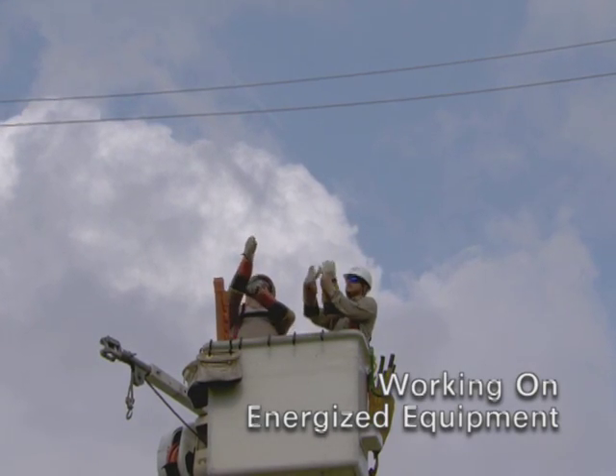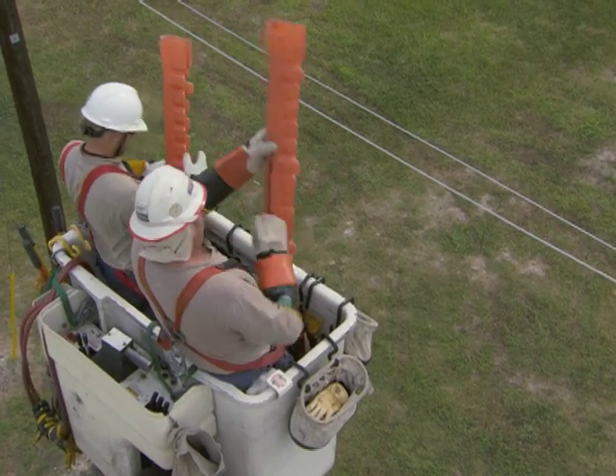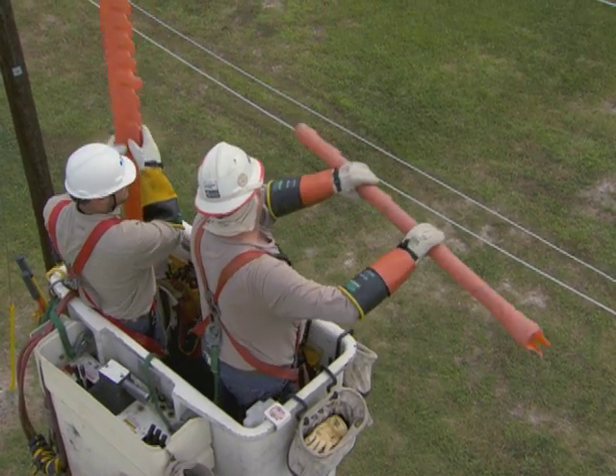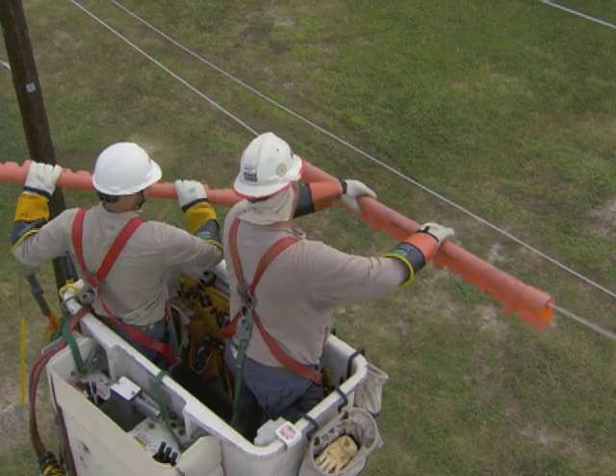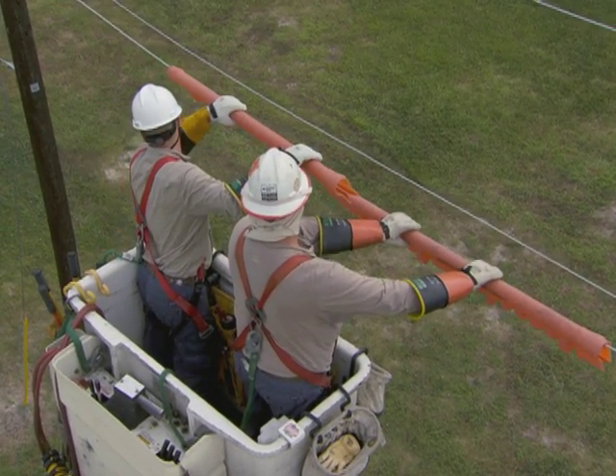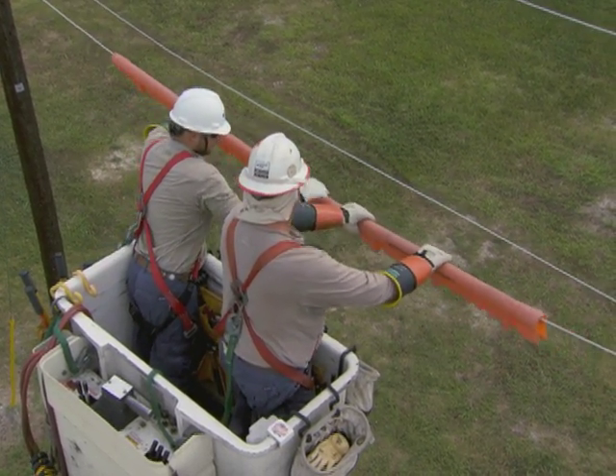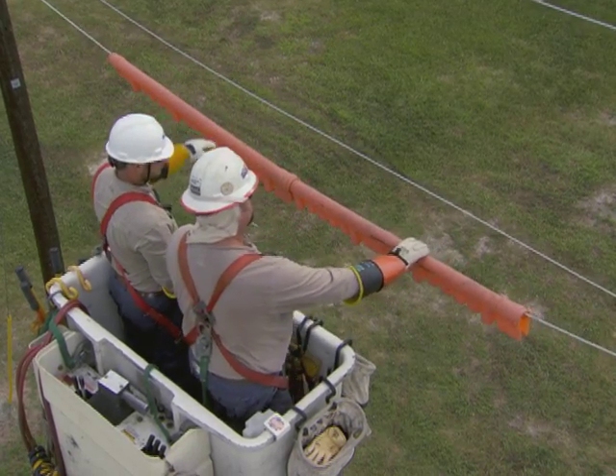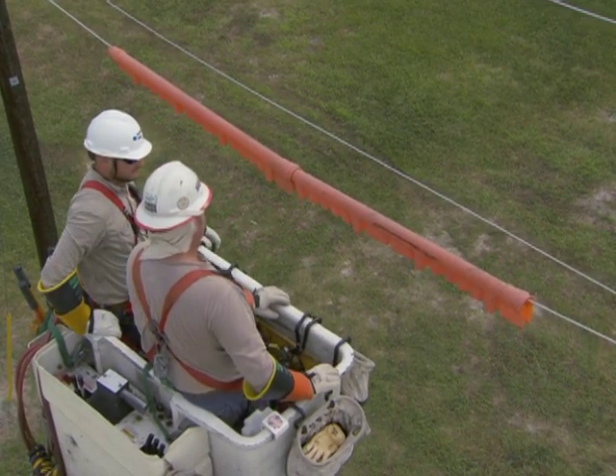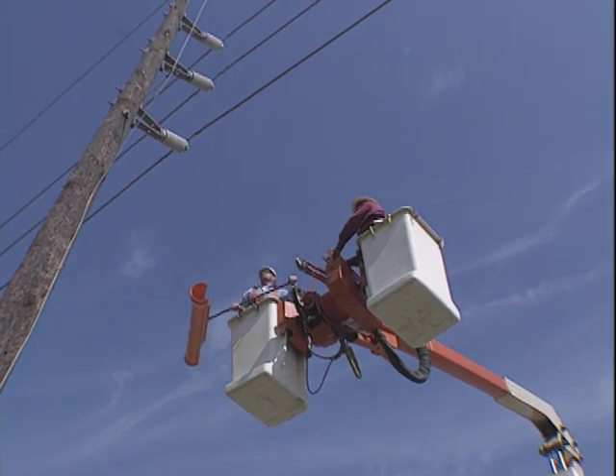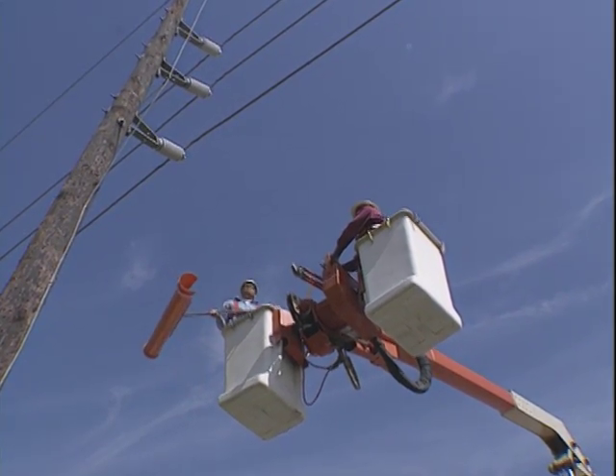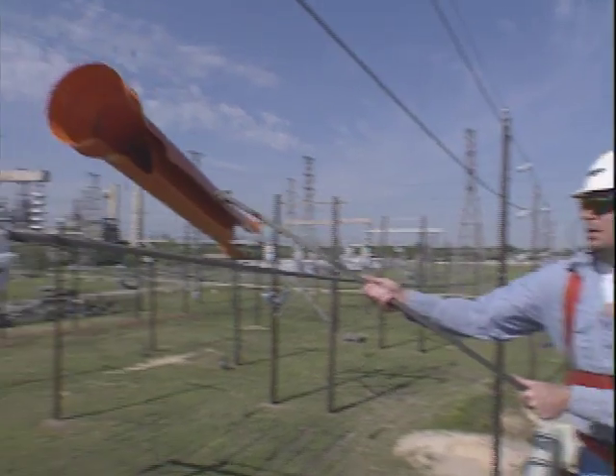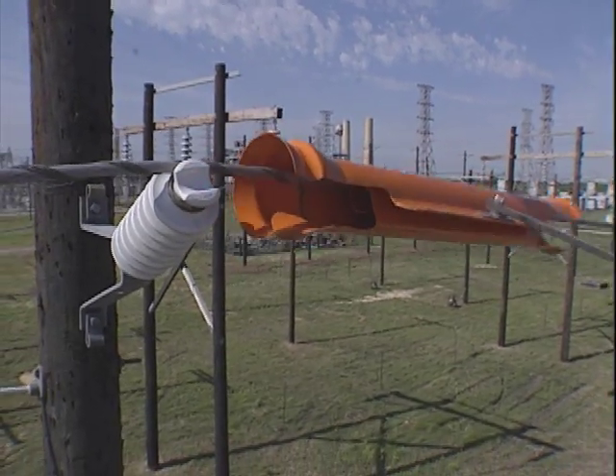When working on energized equipment up to and including 5,000 volts, you must wear rubber gloves with the correct insulating value. Rubber gloves are required when working from an insulated aerial device on voltages up to but not exceeding 7,200 volts. Live line tools must be used on voltages at 7,200 volts while working from the pole, or over 7,200 volts from an insulated aerial device.